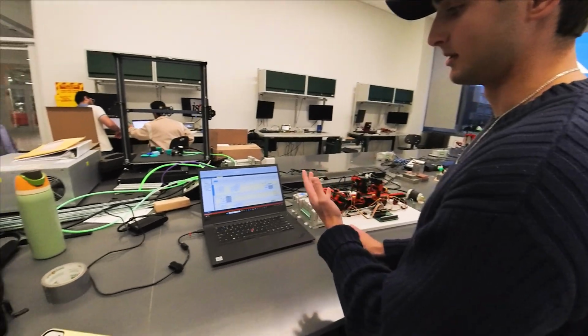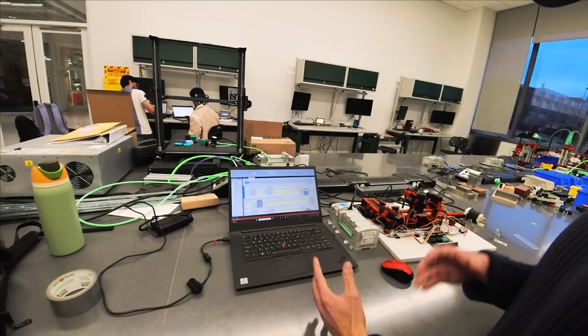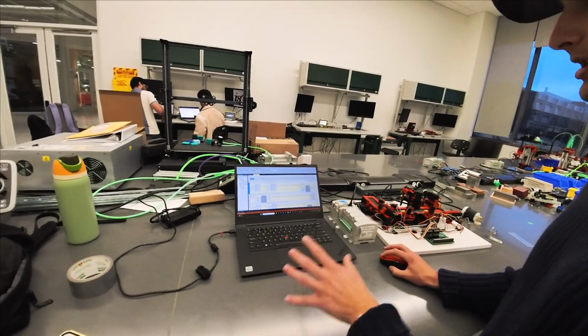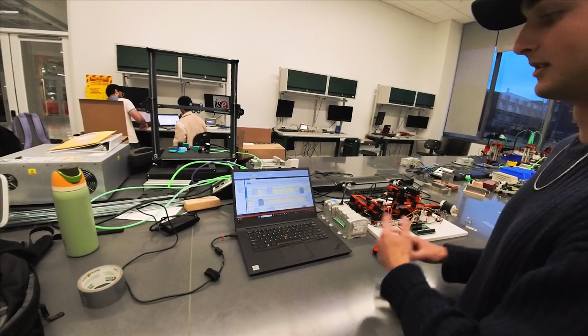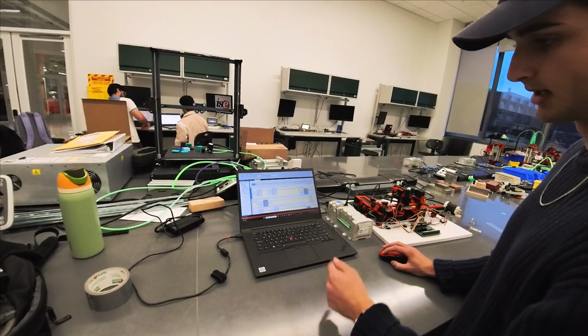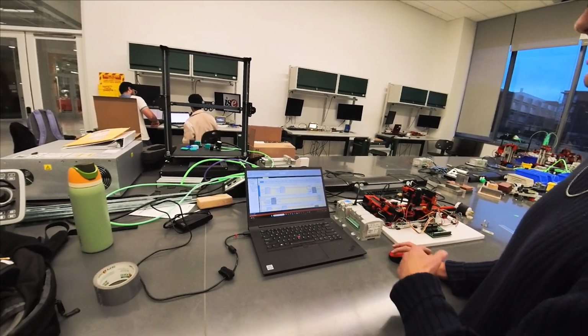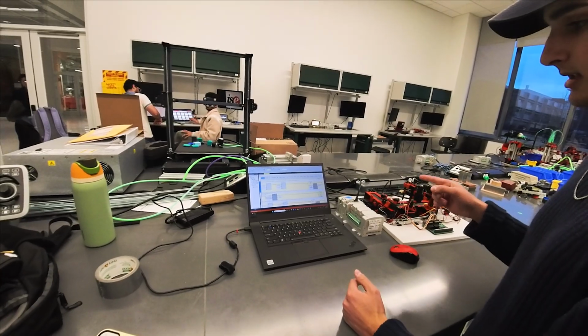This does 2 things. It tells the system to latch on a Boolean tag, which in the PLC marks that there is a blue block, and then it also tallies up the counter, which is the information we really care about. As long as that Boolean tag is set, it can jump to the next line here, which starts the timer connected to the sorter arm and the belts.